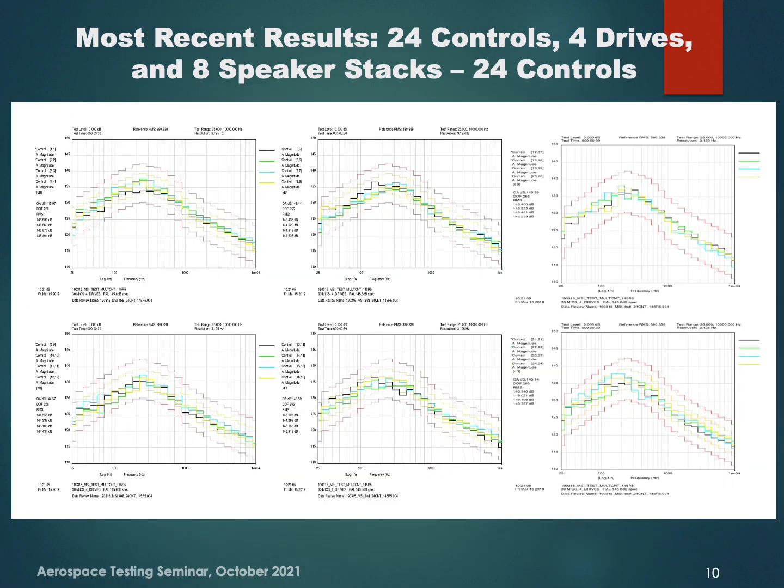The individual microphone responses are shown next in third octave format, all 24 of them. And again, you can see that they are close to the reference and within the plus and minus 3 dB tolerances of the test.